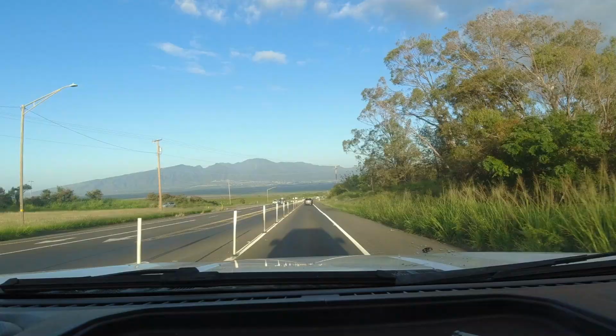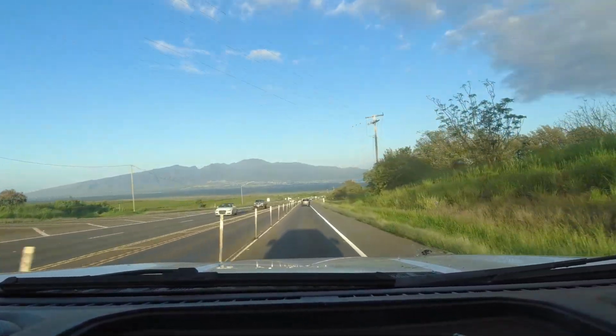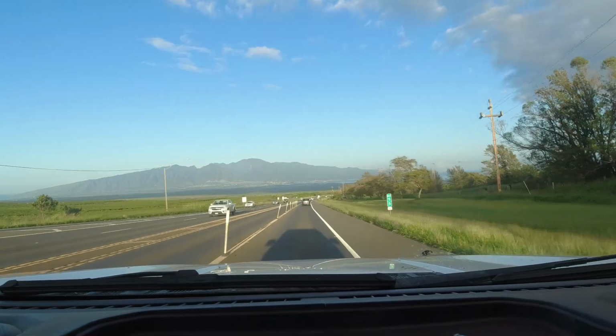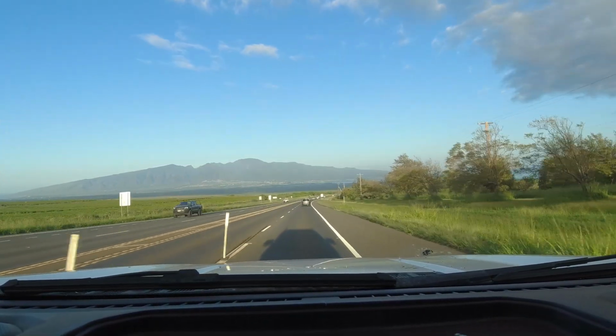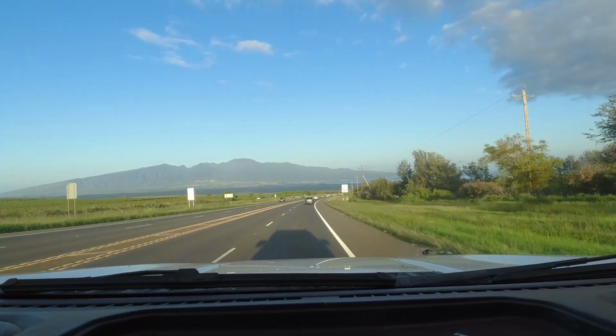There's no utility power at the site. They're currently using, I believe it's a 300 kilowatt generator, 480 volt. It's wired into an MCC with two VFDs. I believe our motors are 125 horsepower, if I remember correctly. We'll get that today. And then with the VFDs, they're using those to do a very slow ramp over about 60 seconds. And they're also using them to control the speed so that they can get just the amount of flow that they want into their system. It's irrigation water system.